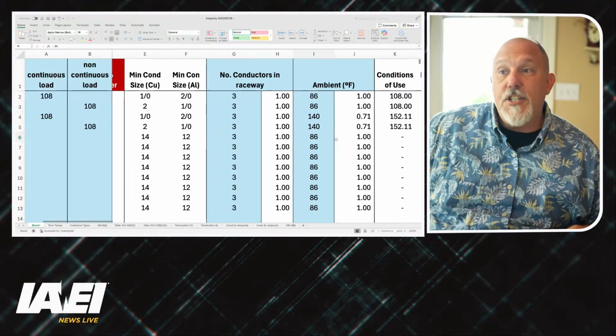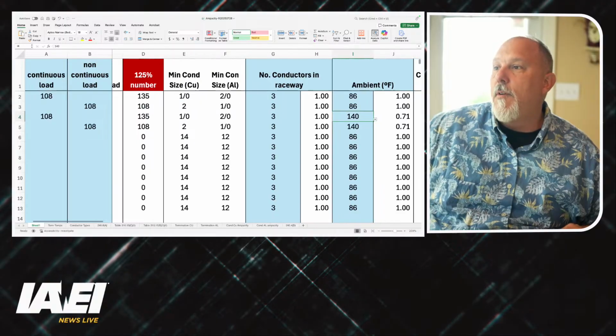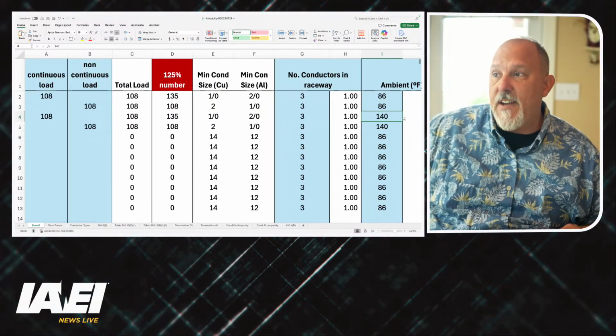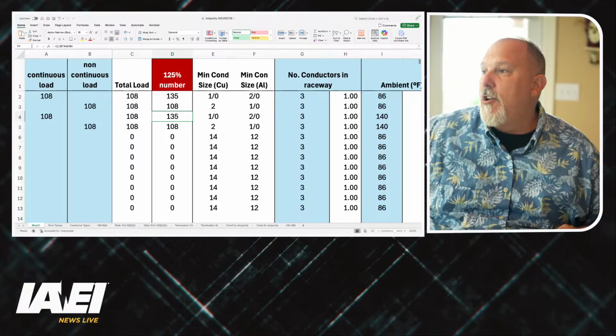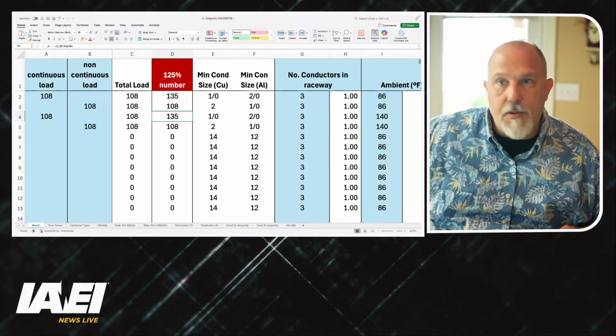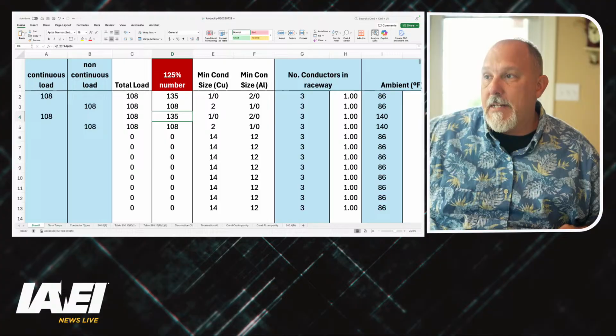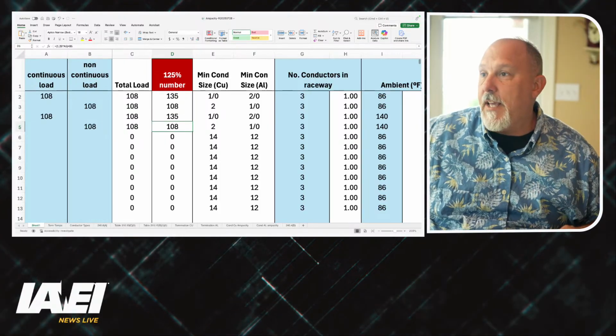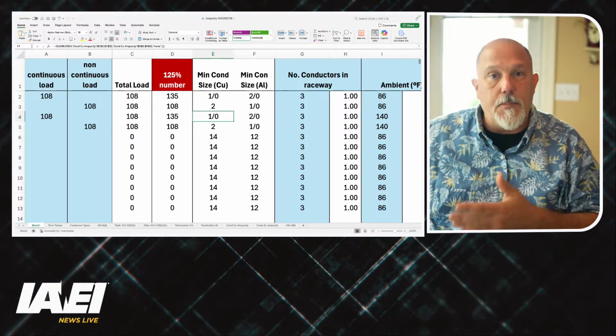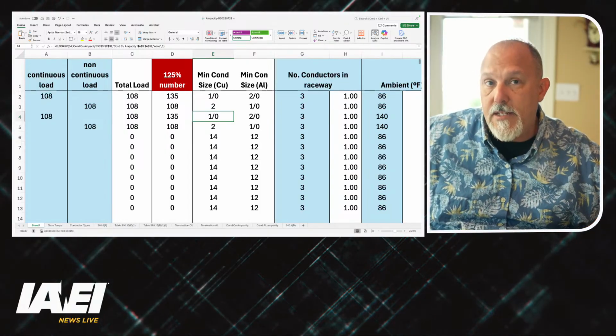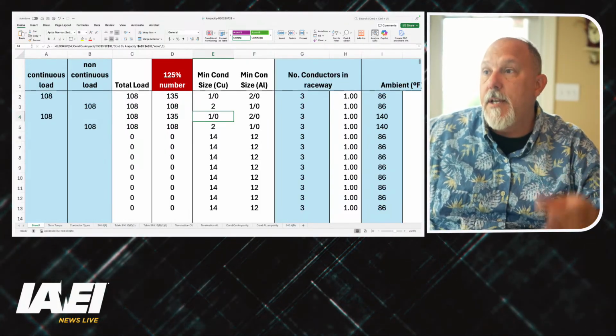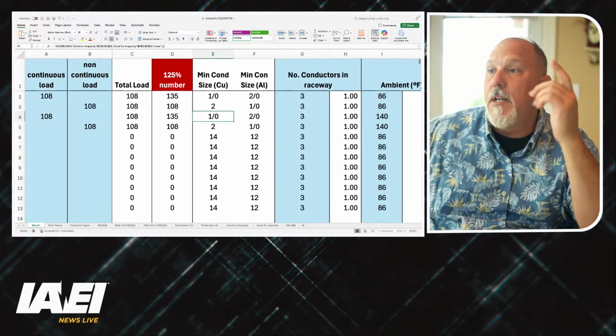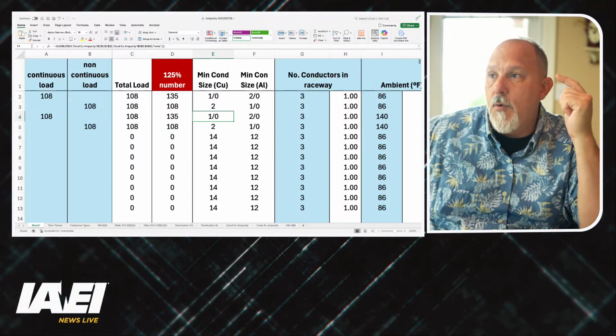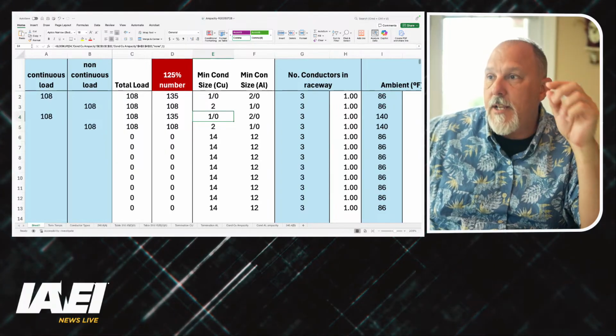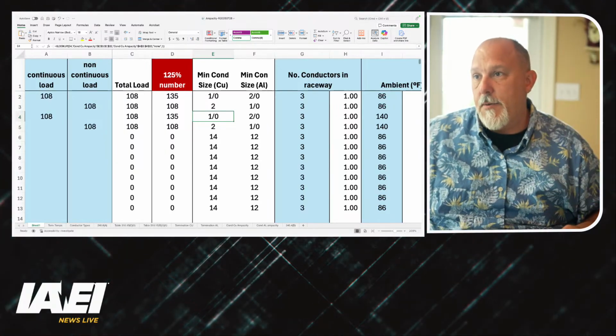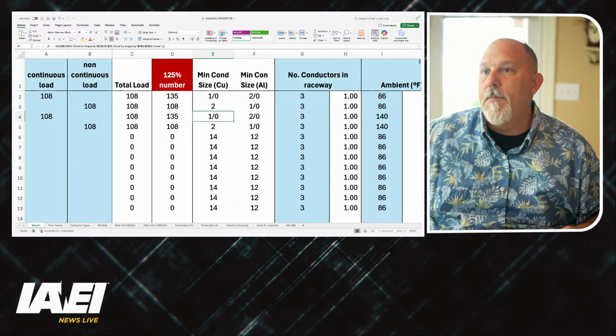So what I just changed was the ambient temperature. The first step, 125%, is exactly the same. For 108 amps of continuous, it's 135. For 108 amps of non-continuous, it's 108. Piece of cake. My largest conductor size based upon that, which has nothing to do with ampacity and everything to do with the equipment based on the 75 degree C column, is 1 aught for the 108 of continuous and a 2 gauge for the non-continuous. And I'm just going to talk copper for now.